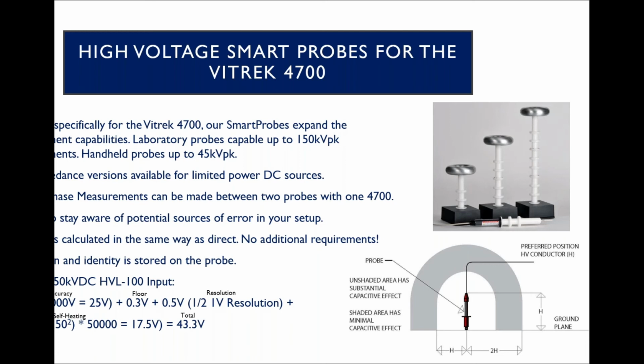So the accuracies are calculated in almost the exact same way as the direct. There's no additional adders. You don't have to take into consideration both the probe and the 4700. These are total accuracies using the probe and 4700 combined. The calibration and the identity of the probes are stored on the probe. That's what makes them smart, so they can connect into any 4700, and the 4700 will automatically know what probe it is and the calibration constants that go along with it to ensure accuracy. It can be used with any 4700.